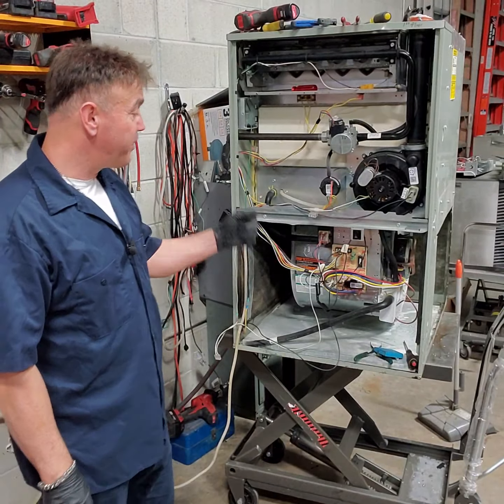This is EAC, electronic air cleaner, if you have one. These are all neutral. XFMR is always the transformer—sometimes it could be labeled PR1, which is primary. And circulator is the blower motor. These are the commons, and then, as we said, we'll move to the blower motor.